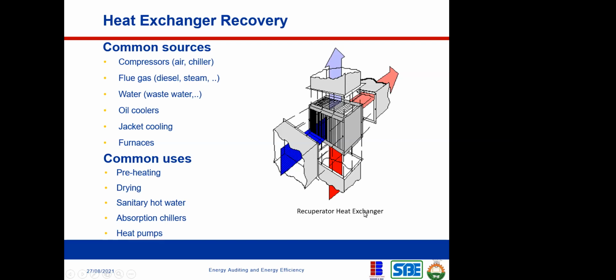So this is a recuperator heat exchanger. When I talk about a recuperator, I'm talking about using air to extract the heat from your exhaust gas. I'm just using an example that we can easily relate with. You have your diesel generator, you have the exhaust pipe. You now have something that passes air through that pipe, so that when the air is coming out from that pipe, the air is now hot, right? That is now what is happening in a boiler. We use air to extract the heat that is going out through the exhaust pipe, and we inject that hot air into the combustion chamber to make the combustion efficient.